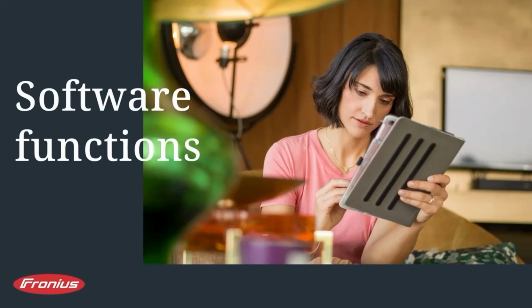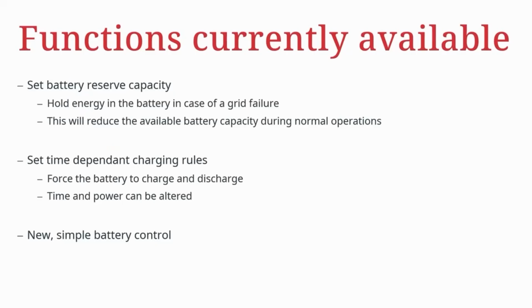In terms of the backup solutions, we need to consider the software functions that are available with the devices. We can set the battery reserve capacity for the inverters. We can make sure that we have a set amount of energy within the battery which is always reserved for a backup scenario. The key thing to consider, of course, is if we use that reserve feature, that energy will not be available on a day-to-day basis. So only use a reserve capacity which is really critical on your site, maybe 5 or 10% above the minimum charge limit, just to ensure that you can keep the lights on and keep essential loads running.